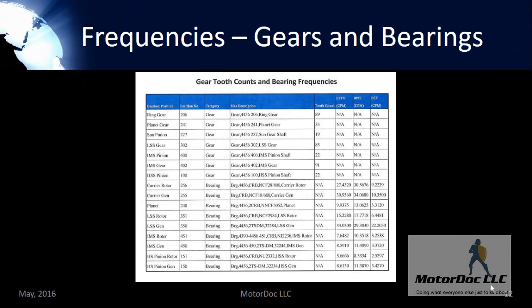Finally, knowing the gears — including all of the different components within the gears and the bearings — I can calculate the different frequencies just by using the speed from the machine. Also, if I have the slot count or rotor bars, if it's an induction machine, and the stator slots, I can calculate virtually anything from the machine.